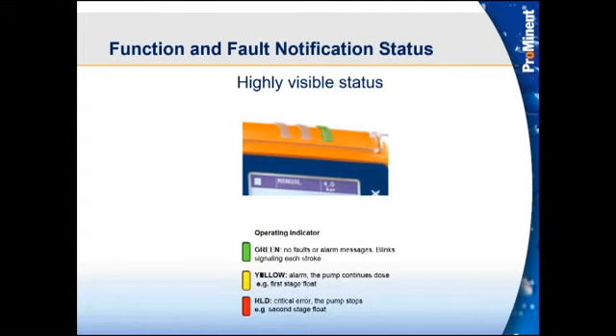The green status light, which is a normal status if the pump's going good, will blink for each stroke, just like all our pumps. If you have it doing, say, 3 continuous strokes a minute, which is very slow, it will give a steady strobing, letting you know it's doing that instead of strobing just every time. It will give a nice strobing, letting you know it is discharging. Okay, so those are very visible from any location.